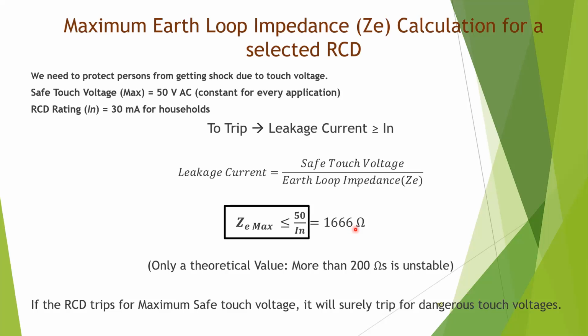which is a very high value, but this is only a theoretical value. More than 200 ohms is unstable, because soil resistivity changes depending on the season of the year. In January it will be low, in August it will be high, depending on the wet and dry conditions. So usually we say more than 200 ohms is unstable, so we cannot define this as the highest value. This is just for your knowledge. If I gave you a question saying 100 milliampere RCD, what is the earth loop impedance, you can use this equation to calculate the maximum earth loop impedance.